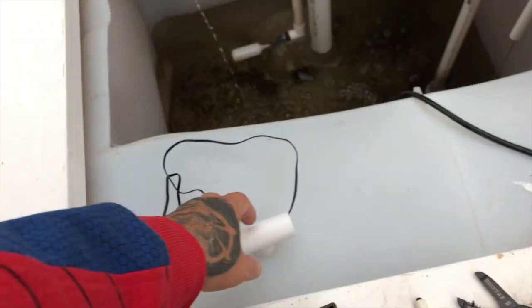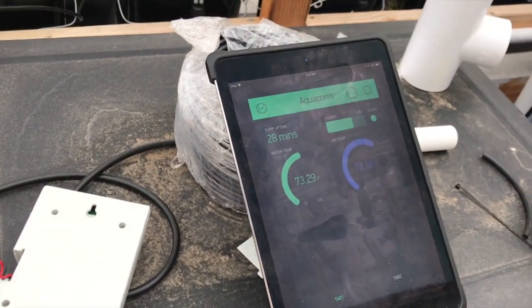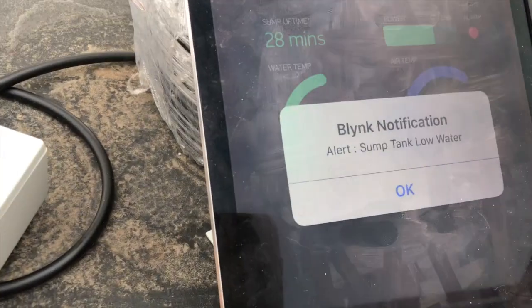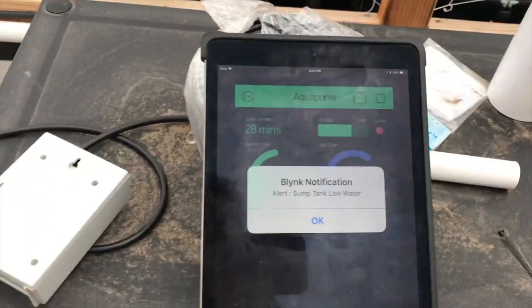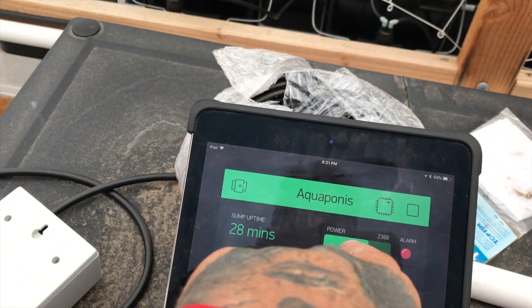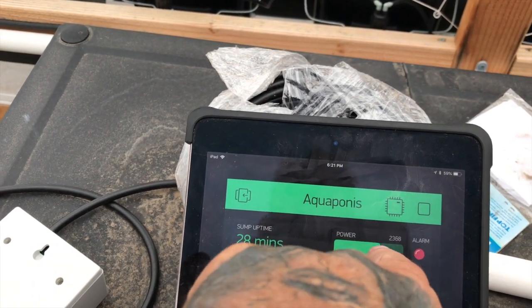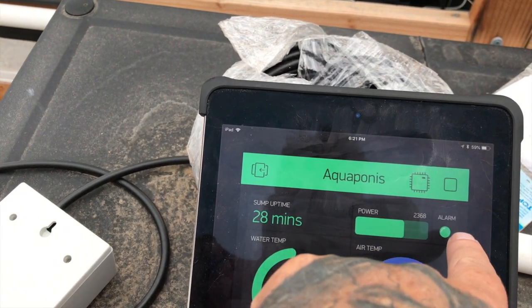I'm going to pull this switch to simulate that the water has drained out. It does take a moment because I have a delay built in — but there we go, we've got the alarm notification and the LED is red meaning it's an alarm. I'll put the switch back down. In a few seconds this will go back to green. I also took out the number display for power — there's still a number there — and I put a bar graph so as it starts to go down you'll see it change. It went to green — switch is fine.